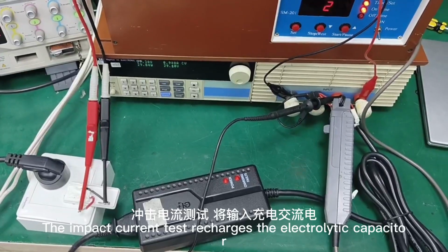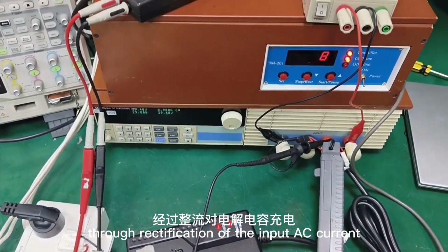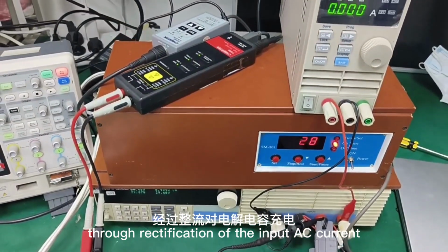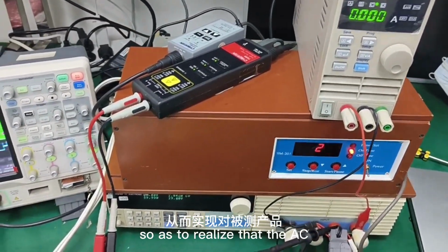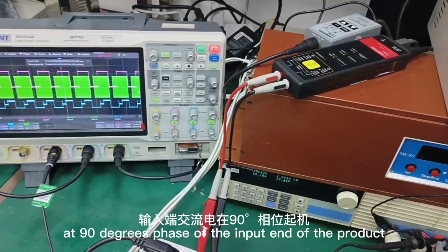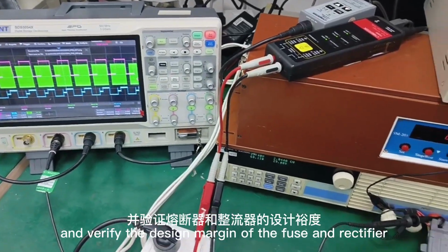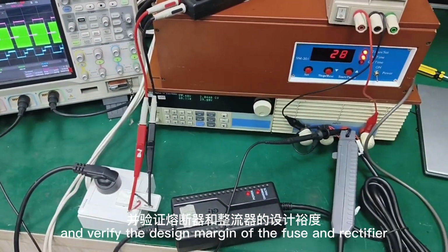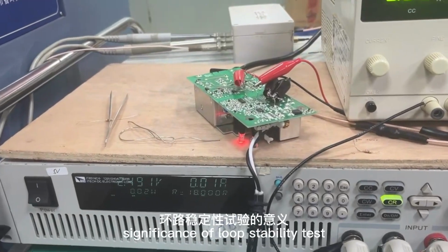Impact current test: recharges the electrolytic capacitor through rectification of the input AC current, so as to realize the AC at 90 degrees phase of the input end of the product under test, and verify the design margin of the fuse and rectifier.